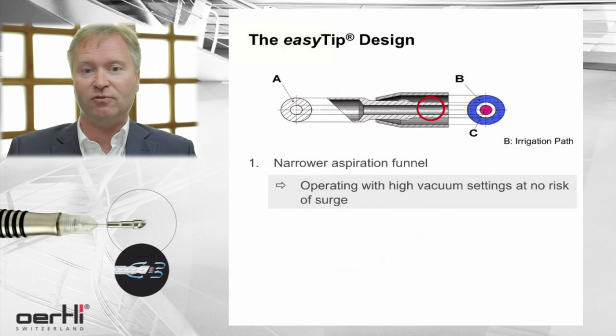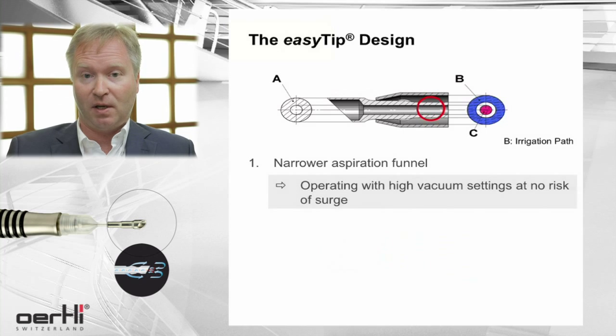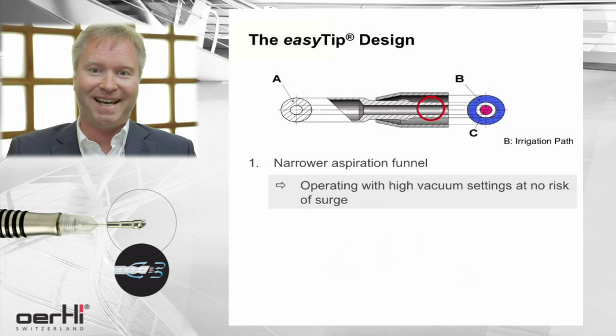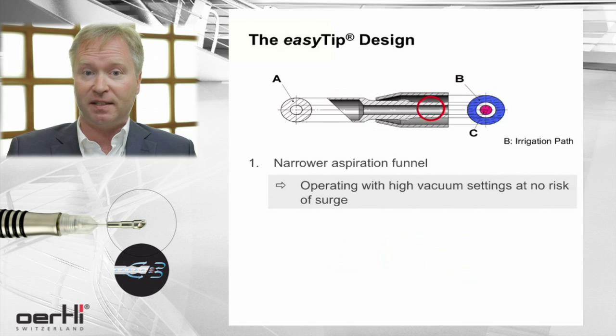You do not have to be afraid of surge at all. On the other hand, if you do have a narrower aspiration funnel, active aspiration is not affected by this, so you can apply very high vacuum settings.